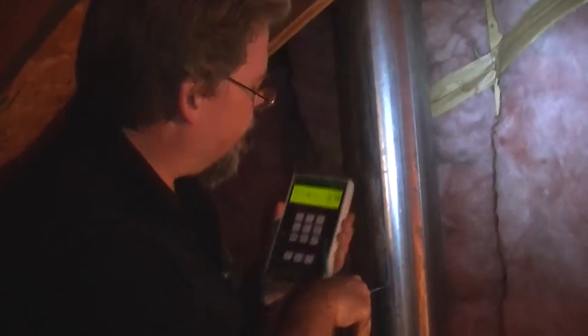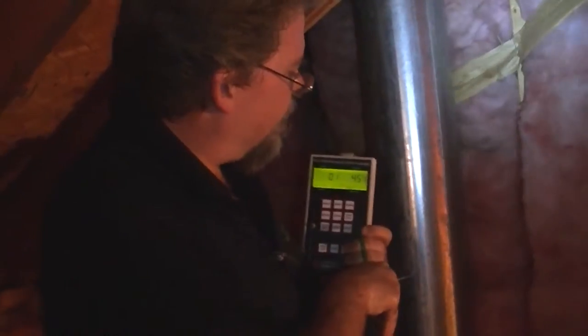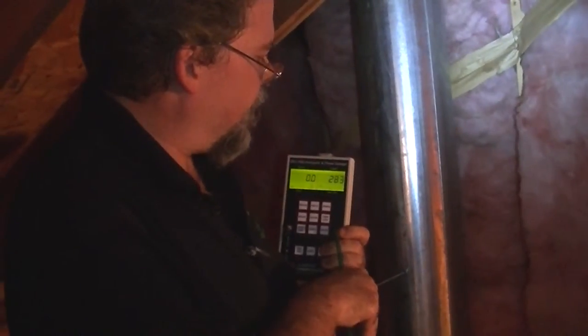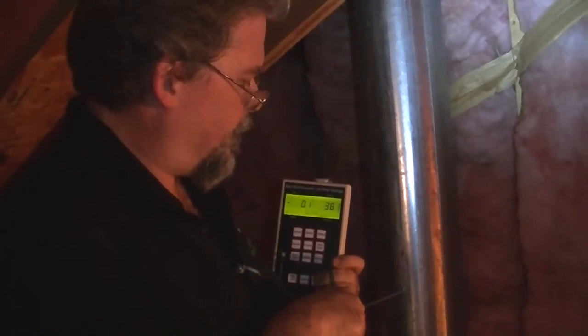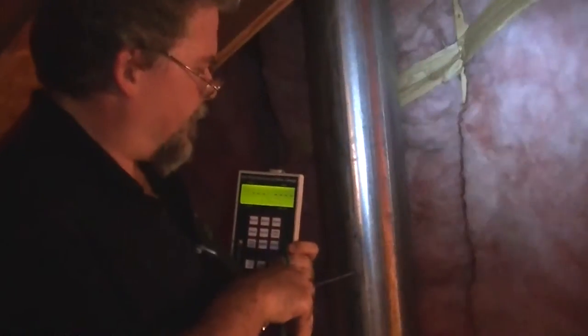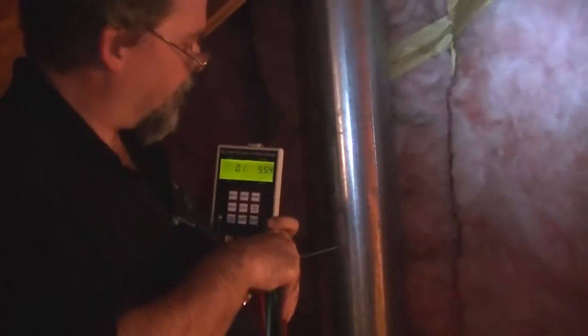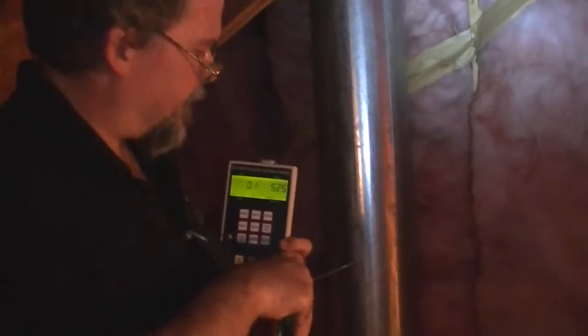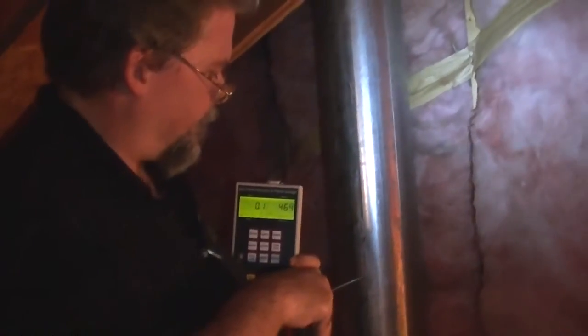I take the reading up against that edge: 451. Withdraw the tube: 295. Withdraw the tube: 381. Withdraw the tube: 475, 452, 525. Withdraw the tube so it's up against this end: 463. I'll take the average of those readings to get the feet per minute.